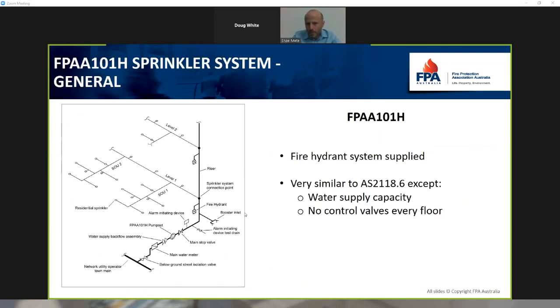The water supply capacity has a concession, which we'll talk about in a second, and there are no control valves on every floor. So at this sprinkler system connection point that feeds the sprinkler system on the floor, there is no control valve on each floor as we go up. It's one system, in a similar way that a 2118 Part 1 system would protect this building. It also wouldn't have control valves on every floor or be required to have them.